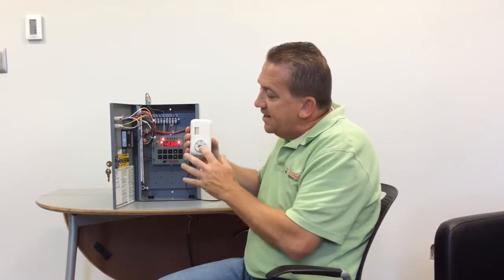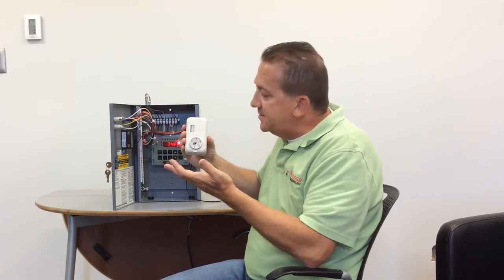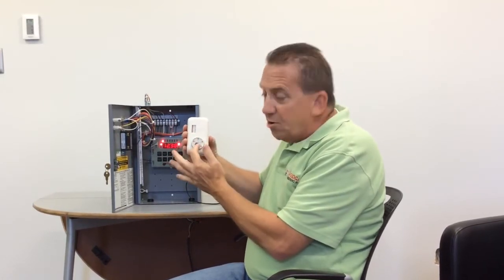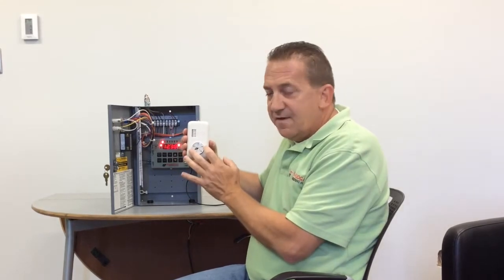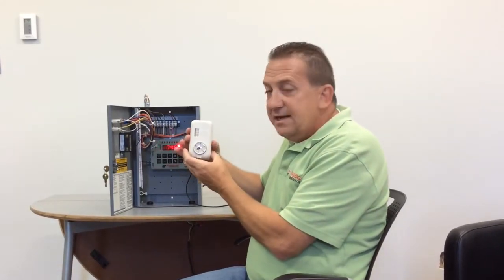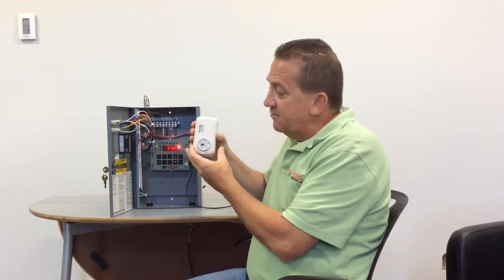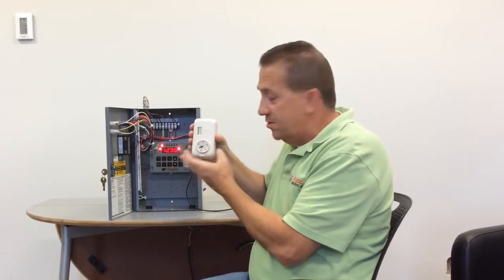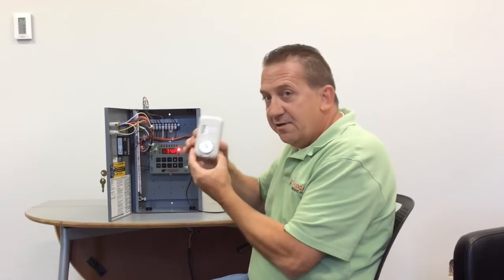And what this control does is it tells the amplifier up in the heater whether it needs make-up air or space heat. So whenever this dial is satisfied, let's just say it's on 70 and it's 72 degrees in the space, it's going to tell the amplifier it needs just make-up air. Whenever it's below 70 degrees, it's not satisfied, it's going to tell the heater it needs space heat, it's going to ramp the discharge temperature up to possibly 160 degree discharge. Now this is a standalone stat.